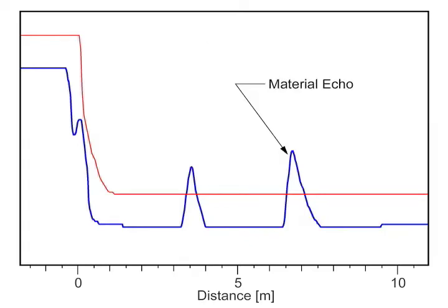In this example, the true material echo is the second echo. The first echo is an echo from a pipe entering the vessel near the top. We confirm this by visually inspecting the vessel and comparing the distance to the pipe to the distance shown on the echo profile.